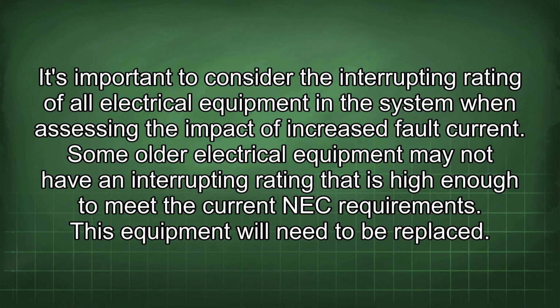It's important to consider the interrupting rating of all electrical equipment in the system when assessing the impact of increased fault current. Some older electrical equipment may not have an interrupting rating that is high enough to meet the current NEC requirements. This equipment will need to be replaced.